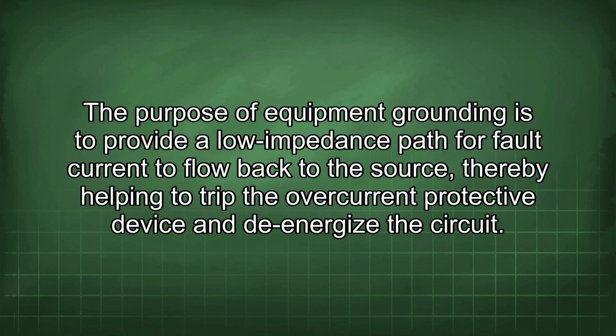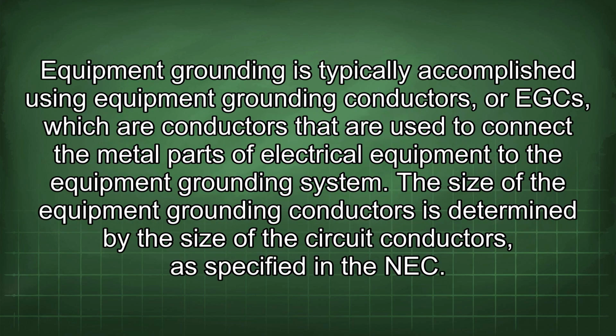The purpose of equipment grounding is to provide a low impedance path for fault current to flow back to the source, thereby helping to trip the overcurrent protective device and de-energize the circuit. Equipment grounding is typically accomplished using equipment grounding conductors, or EGCs, which are conductors that are used to connect the metal parts of electrical equipment to the equipment grounding system.